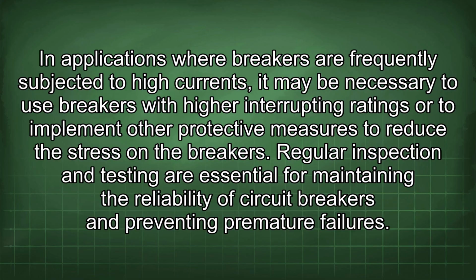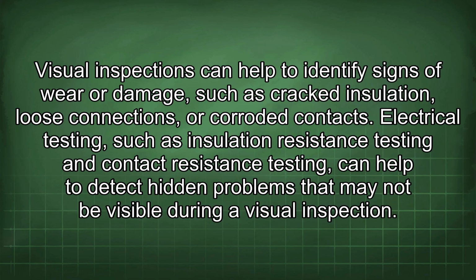In applications where breakers are frequently subjected to high currents, it may be necessary to use breakers with higher interrupting ratings or to implement other protective measures to reduce the stress on the breakers. Regular inspection and testing are essential for maintaining the reliability of circuit breakers and preventing premature failures. Visual inspections can help to identify signs of wear or damage, such as cracked insulation, loose connections, or corroded contacts. Electrical testing, such as insulation resistance testing and contact resistance testing, can help to detect hidden problems that may not be visible during a visual inspection.